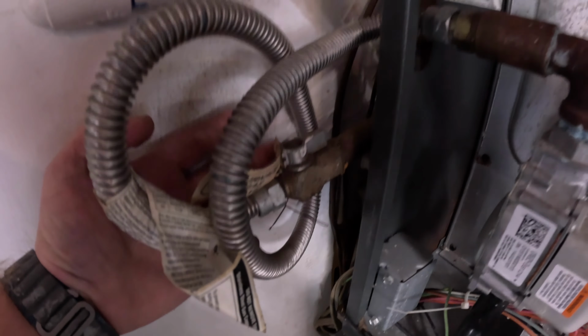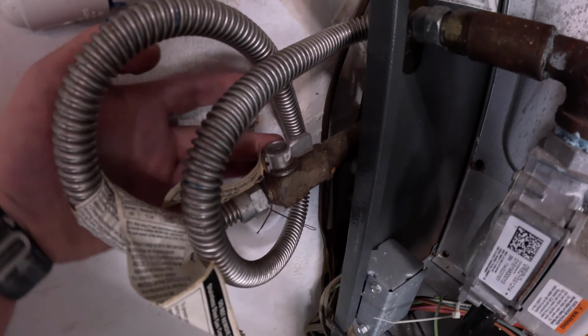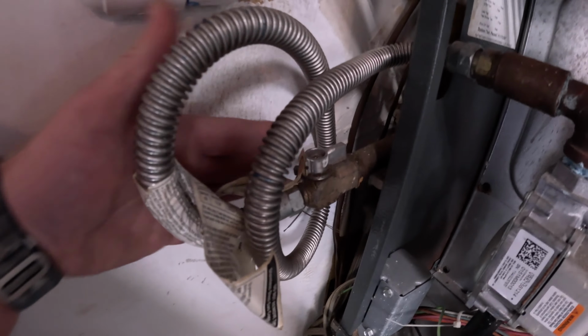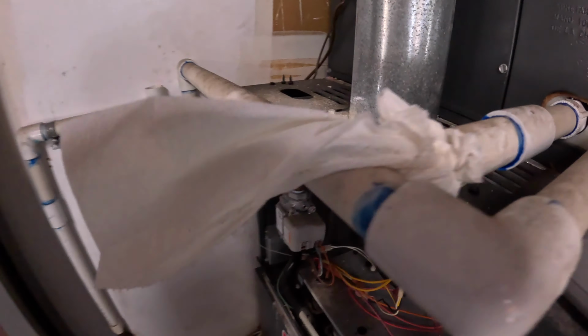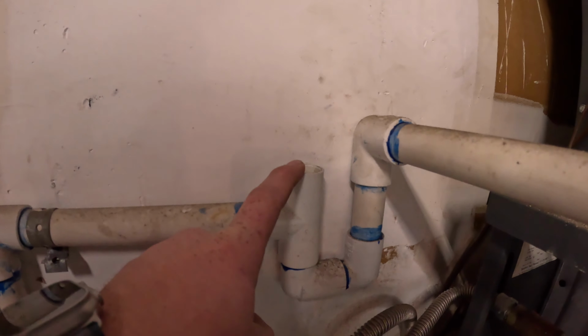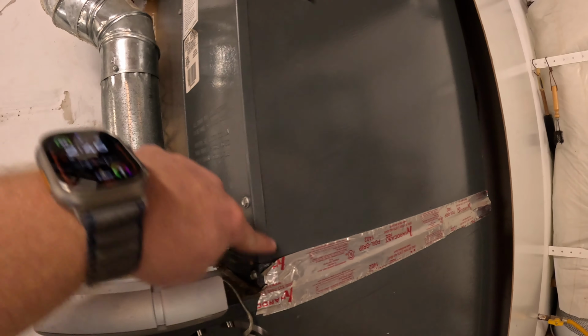There is no sediment trap. This gas valve was not replaced when the furnace was—not necessarily an issue, just kind of lower quality work. This drain is plugged up with some paper towels. This vent right here needs to be higher than where our drain pan sits.